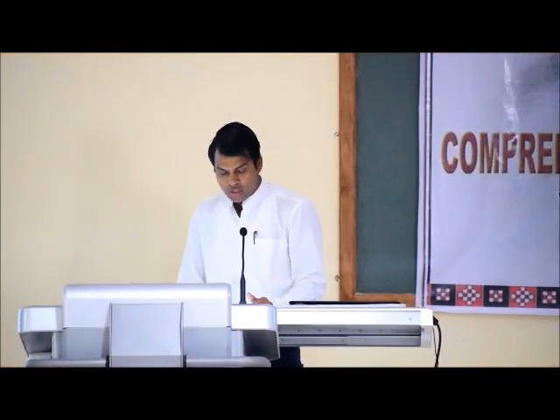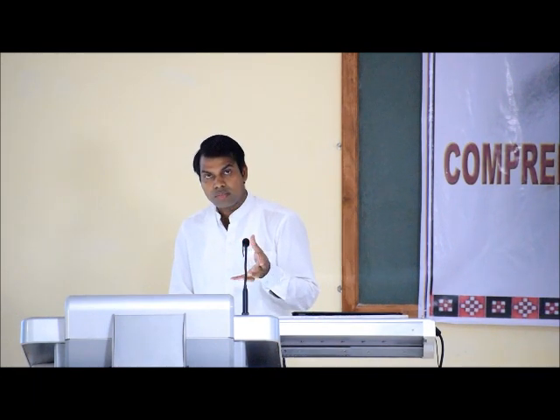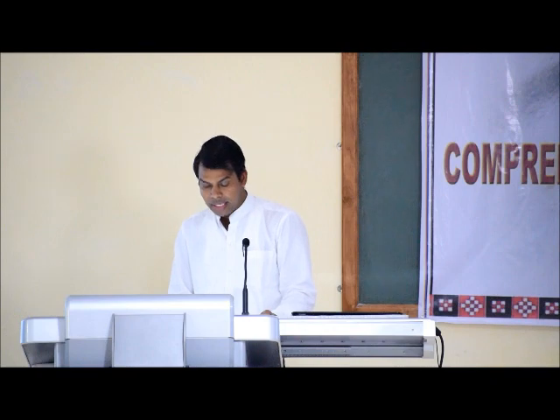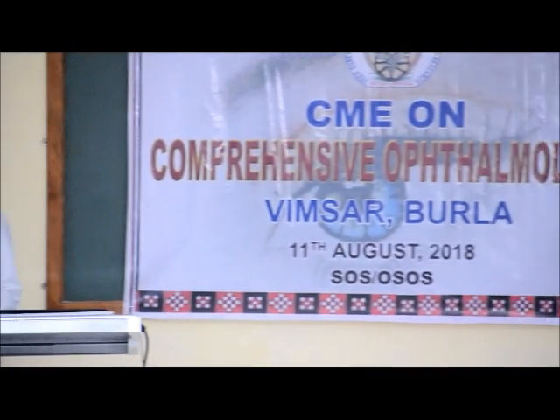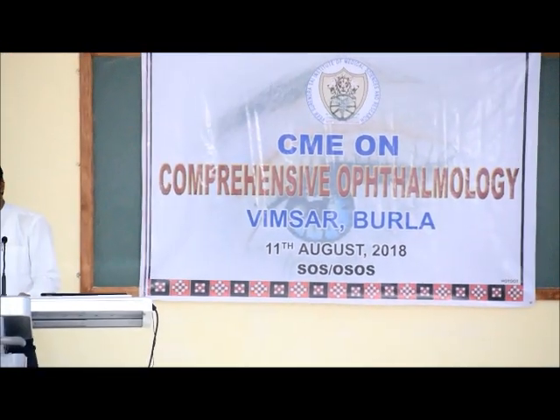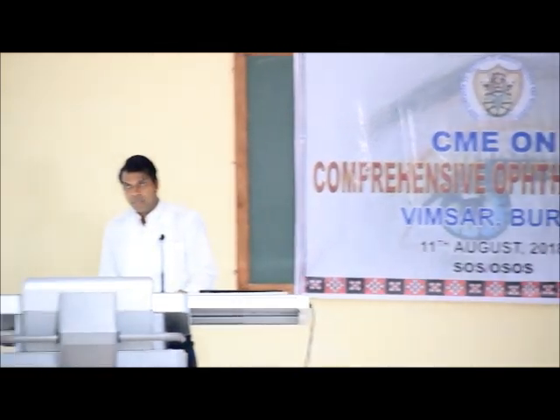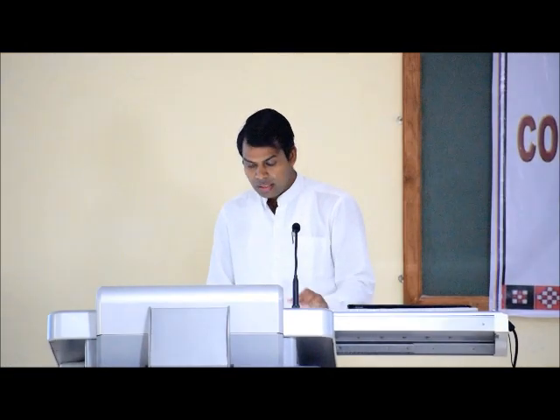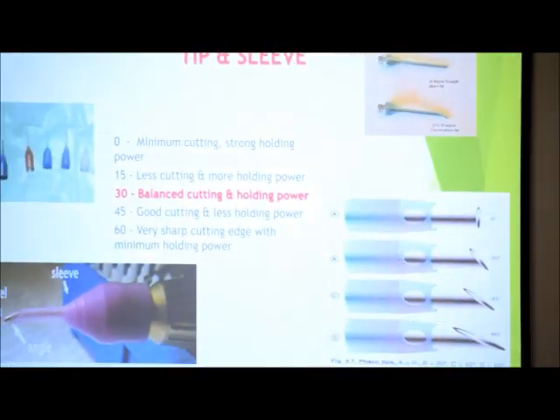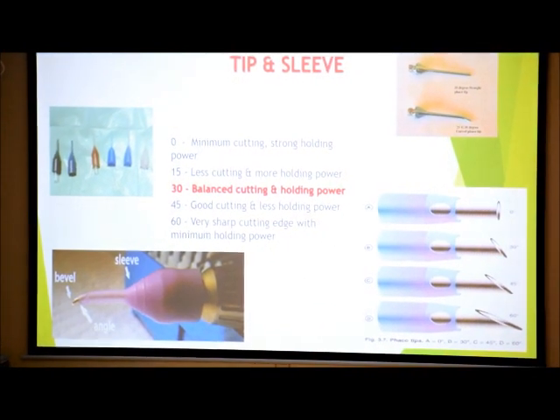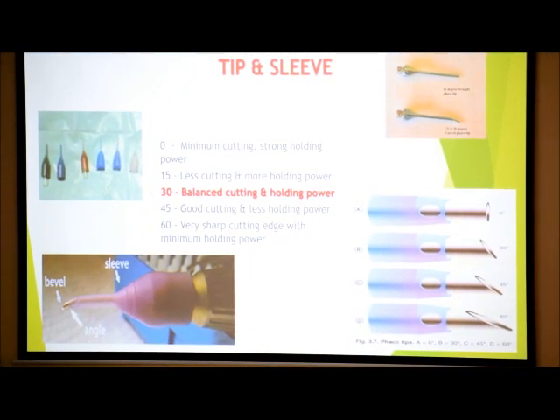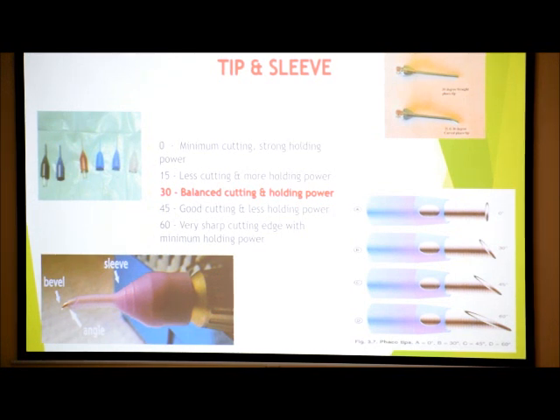Tips I have already told: 0 degree, 15, 30, 45, 60. 0 degree exerts maximum holding, but cut rate is very less. 15 degree, less cut, more holding power. 60 degrees is very sharp and usually used for grade 4 or grade 5 type of cataract, because the cut rate is very high but holding is very less. So 30 degree tip is called a balance tip because it is optimally used for holding as well as delivering the cut rates.